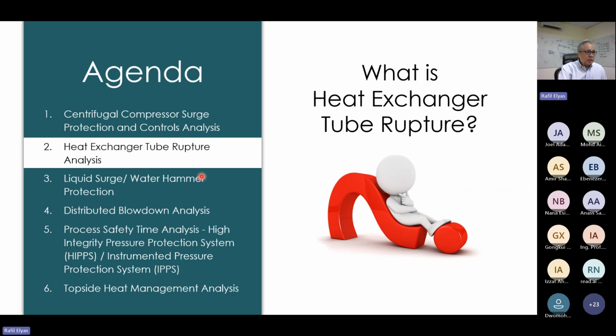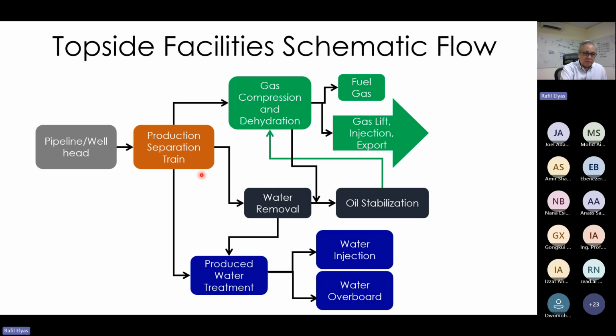Okay. So the next example I'm going to talk about is a heat exchanger tube rupture, another case that we've done for design. This is quite an interesting case because it's a design, but it was actually an FPSO which was being redeployed to a new field. So the pressures and compositions were different. So the heat exchanger manufacturer wanted to ensure that the position and the location of all of the relief systems on the heat exchanger could address any potential tube rupture situation and could protect the heat exchangers from potential overpressure.